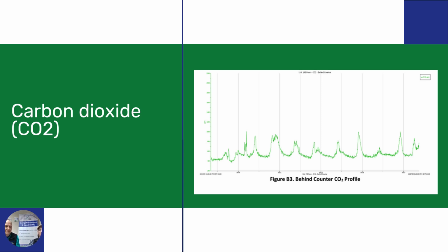But in all seriousness, this is a set of data points that when we put this logger in a place, whether it's a gymnasium, a conference room or an office, we can see upticks in CO2, and that is simply something we give off every time we talk, every time we're breathing. And so we can see, hey, is this a densely occupied space? Is it occupied a lot? Is it occupied infrequently?